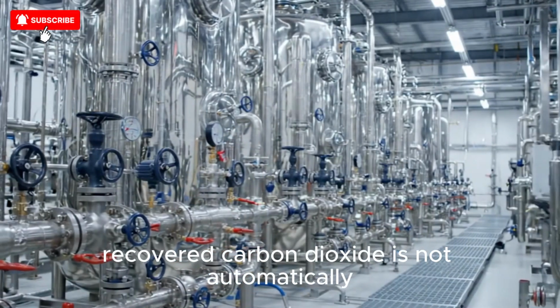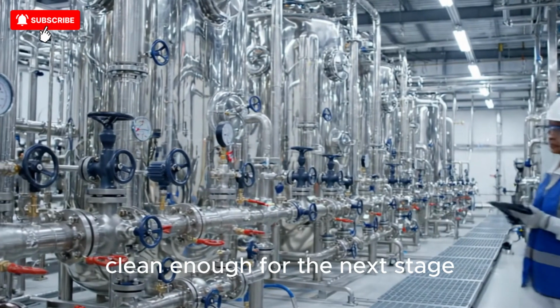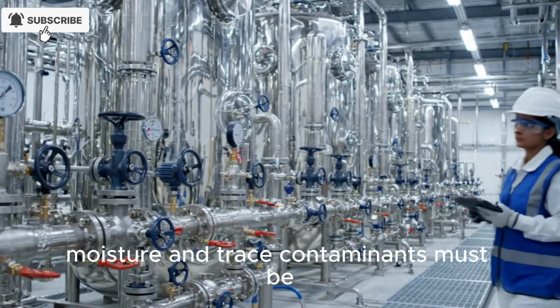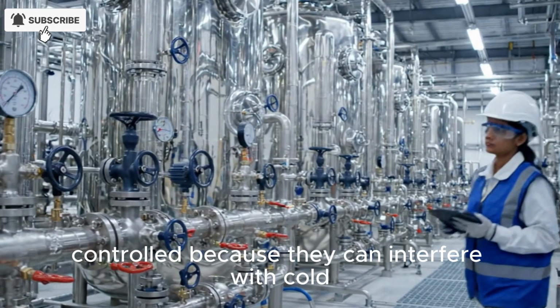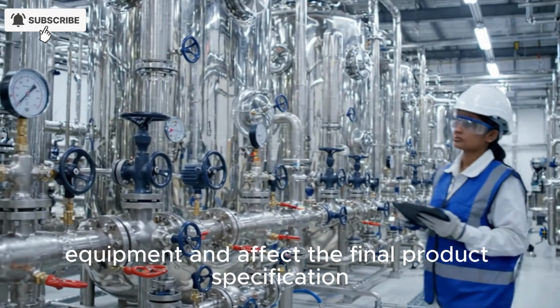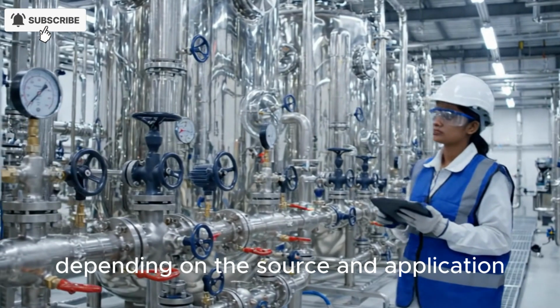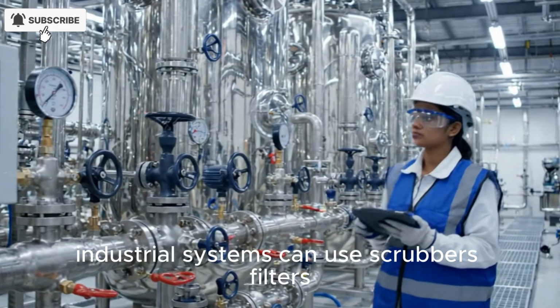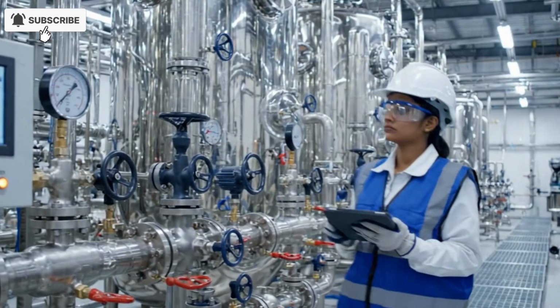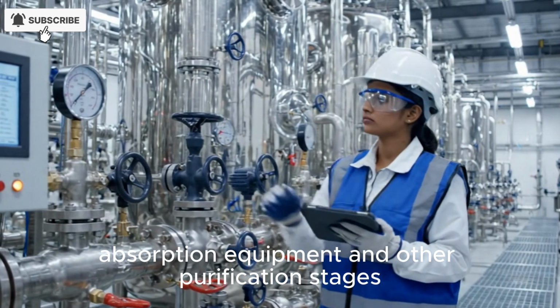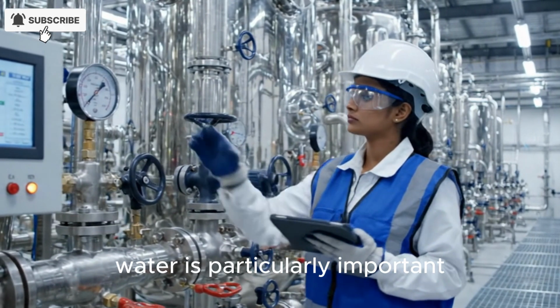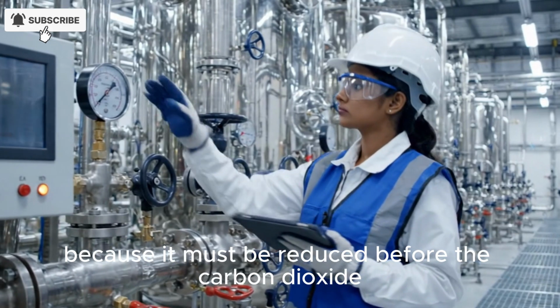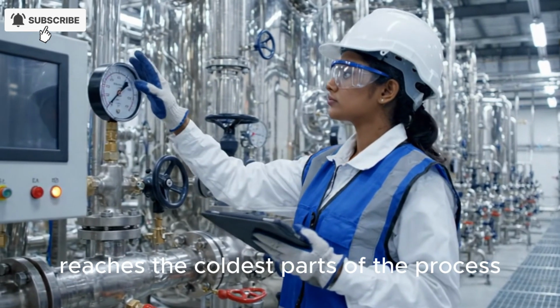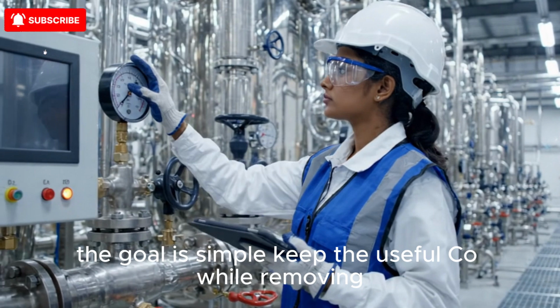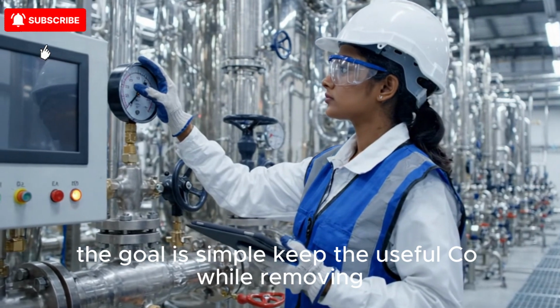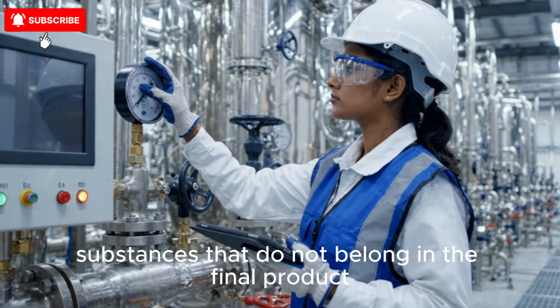Recovered carbon dioxide is not automatically clean enough for the next stage. Moisture and trace contaminants must be controlled because they can interfere with cold equipment and affect the final product specification. Depending on the source and application, industrial systems can use scrubbers, filters, adsorption equipment, and other purification stages. Water is particularly important because it must be reduced before the carbon dioxide reaches the coldest parts of the process. The goal is simple: keep the useful CO2 while removing substances that do not belong in the final product.